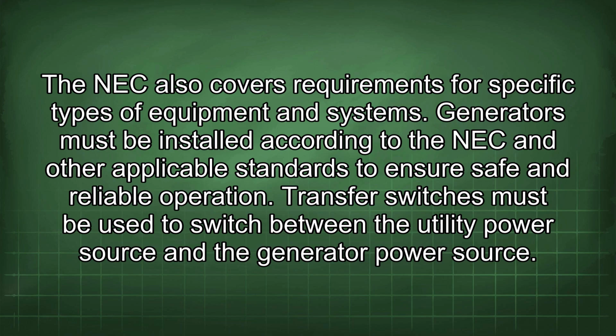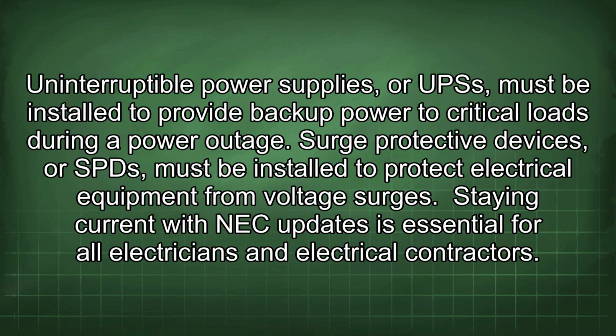Generators must be installed according to the NEC and other applicable standards to ensure safe and reliable operation. Transfer switches must be used to switch between the utility power source and the generator power source. Uninterruptible power supplies, or UPSs, must be installed to provide backup power to critical loads during a power outage.